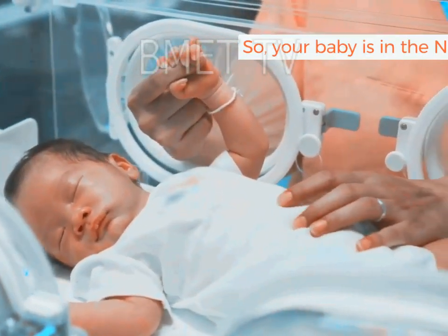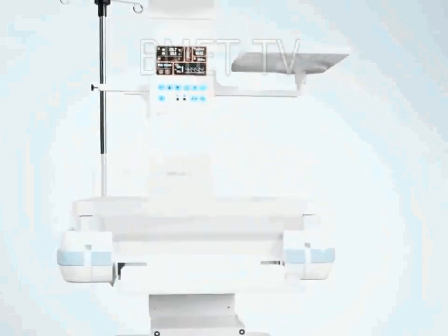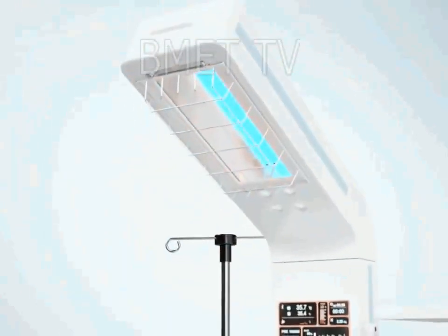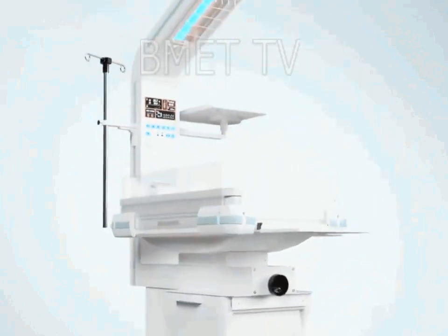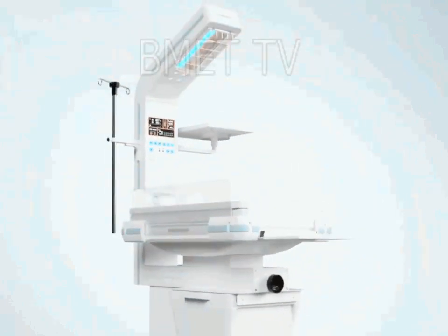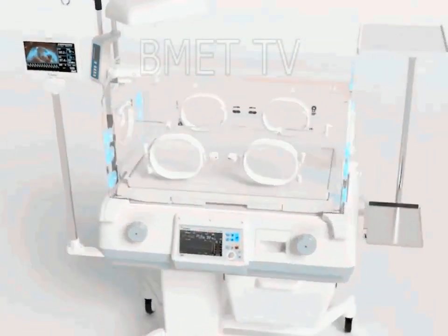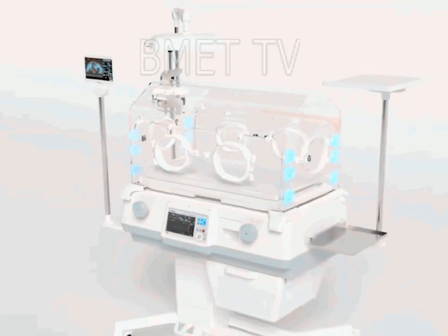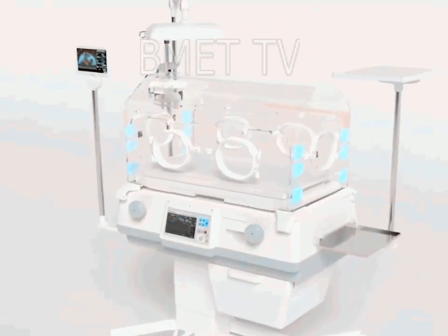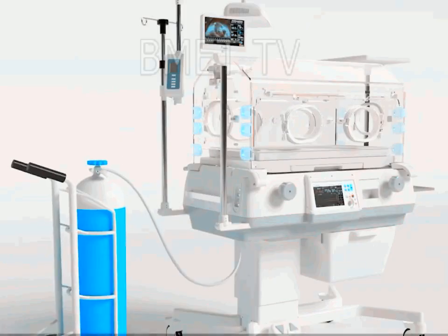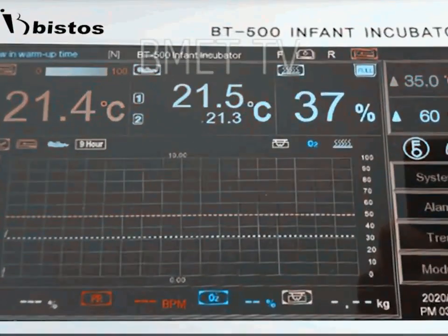Increased ambient humidity, heat shields and clothing have been used to decrease the evaporative or non-evaporative heat loss of infants in incubators under certain conditions. Double-walled incubators, by adding a second inner layer of plexiglass, reduce radiant heat loss. They may also reduce total heat loss, but only if air temperature is controlled rather than skin temperature. The minimal oxygen consumption under a radiant warmer is the same, or perhaps slightly higher than it is for the same infant in an incubator.